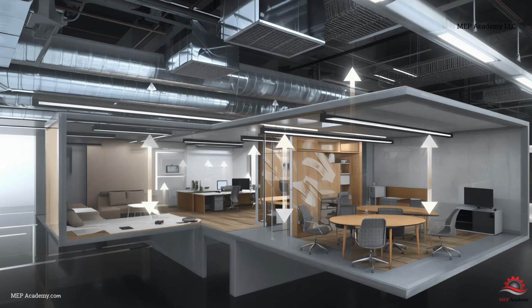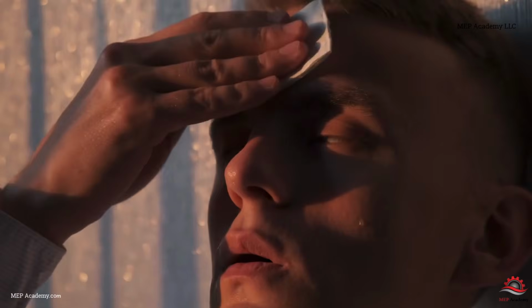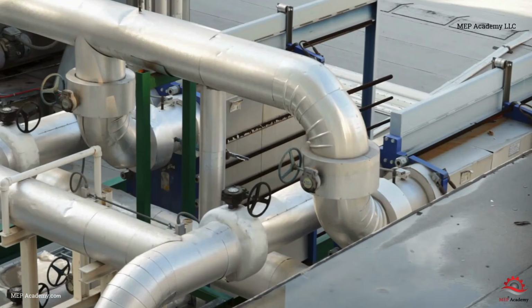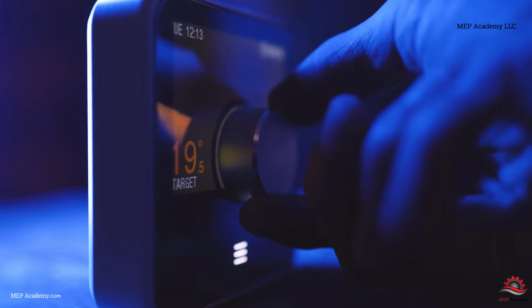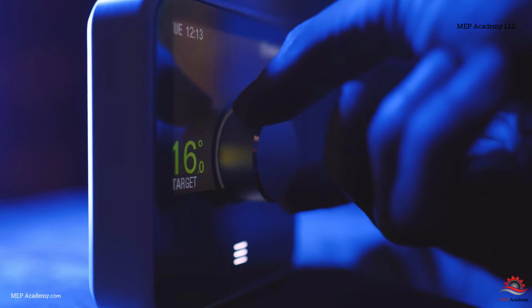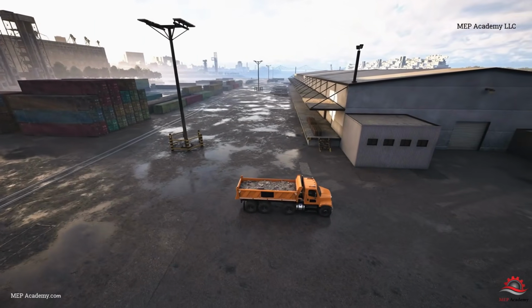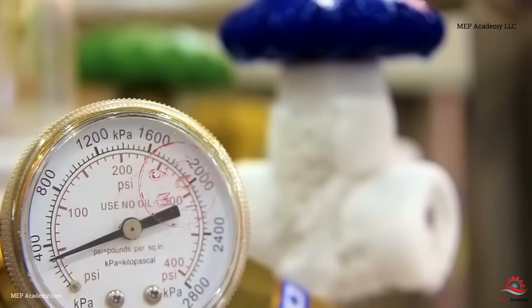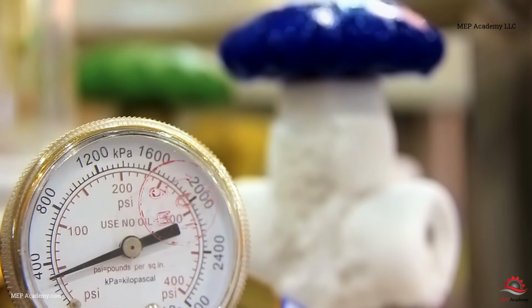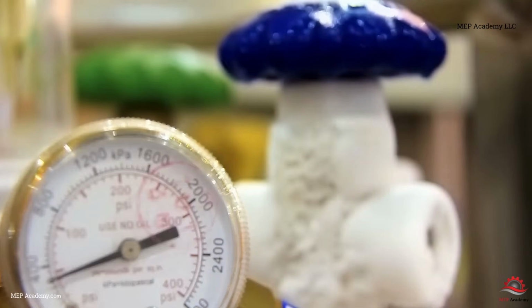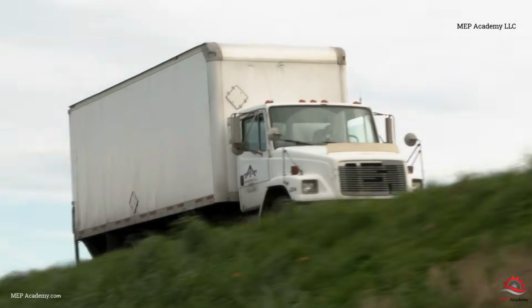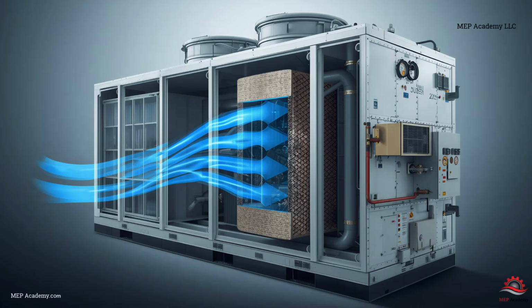The symptoms are often easy to recognize. Certain rooms are always hot. Occupants complain about uneven temperatures. The equipment seems to run continuously. Supply air temperatures look normal, but comfort remains poor. Think of airflow as the delivery truck for cooling. The refrigeration system creates cooling. The duct system delivers it. If the delivery truck never reaches the destination, the cooling never reaches the occupants.